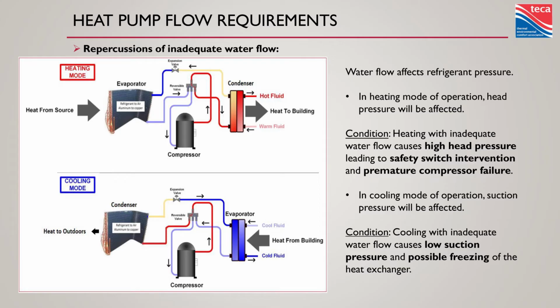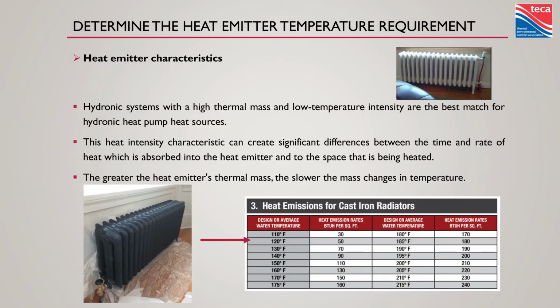Now let's talk about heat emitters. Radiant floor, great, popular. How about cast iron radiators? That was a brand new place in Oak Bay, Victoria that got these fancy refurbished radiators. If you get enough of these together, you can very effectively heat at low temperatures. It's just a surface area versus delta T equation again. So this radiator here is going to give you 50 BTU a square foot with 120 degree average water temperature. But if we were running that at 185, it'd give us 180 BTU a square foot. So size them based on the water temperature you're working with. You can do that with cast iron rads, you can do that with panel rads.